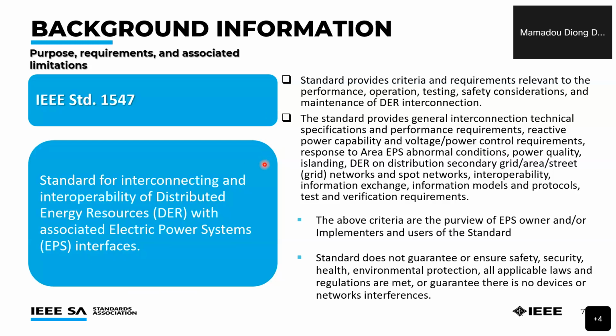All the criteria in standard 1547, although many DER manufacturers follow them to the letter, are still within the purview of the EPS owner — meaning the electric power system or grid owner, or those implementing requirements on how to apply the standards in the electric grid. These represent great consensus reached when the standard was written. But at the end of the day, as a utility provider, it's your responsibility to look at other items outside the scope of the standard, such as safety, security, health, environmental protection, other laws, or coordination and planning of load. Those are the purview of the utility owner or the regulators.